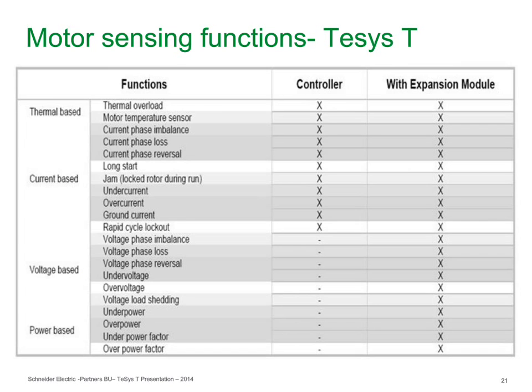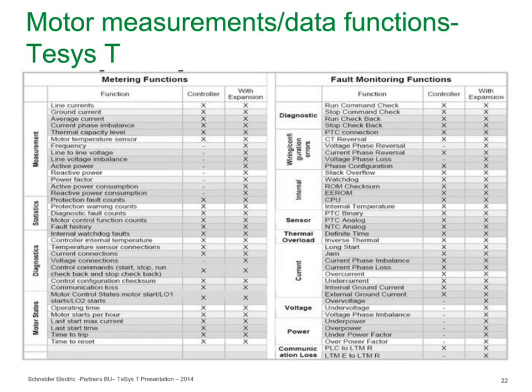This next slide, unfortunately, is the busiest slide that I've got, but it's the most interesting as well, because this is a list of all the metering functions and as well the fault monitoring functions that we can do with TeSys T. This really is the chef's cupboard right here. If I look at the left, what can I meter? I can do active power, reactive power, power factor. It's a laundry list, if you will, of incredible metering functions I can get right out of the overload, and every motor has to have an overload, so it's very convenient to not have a second device to pull this information.